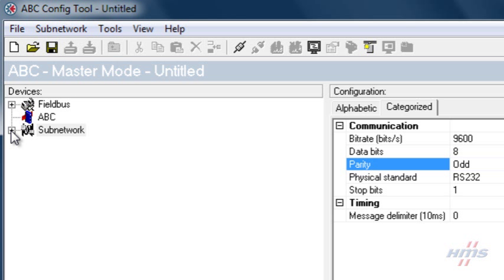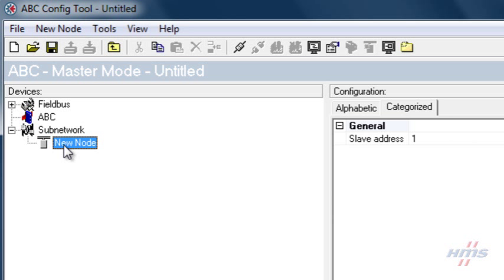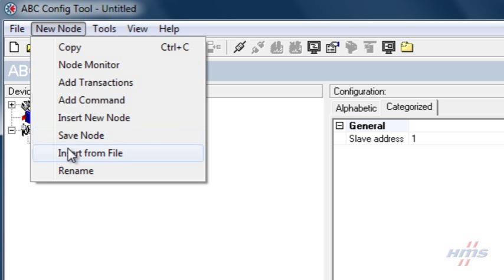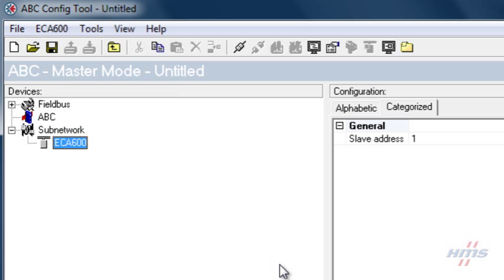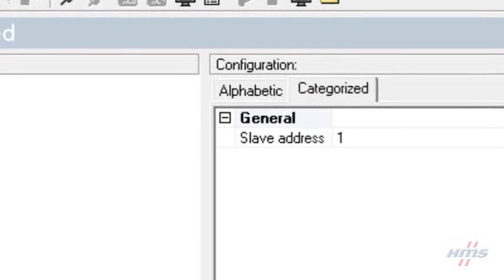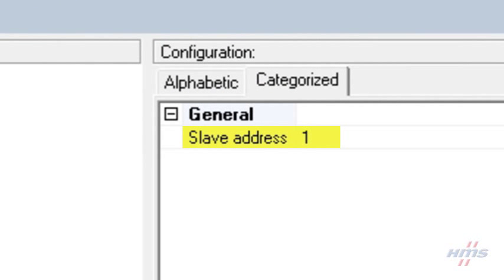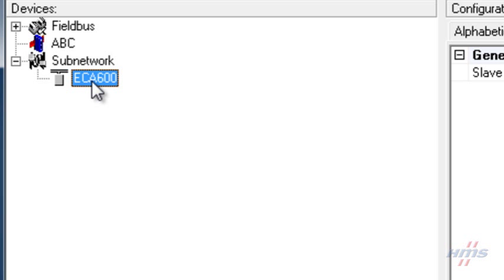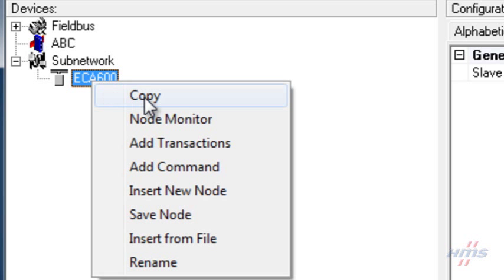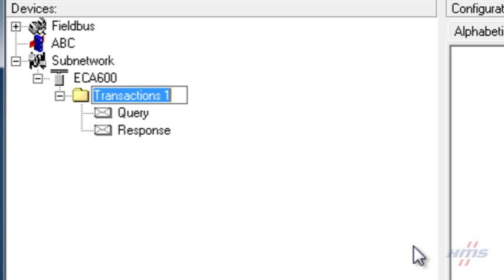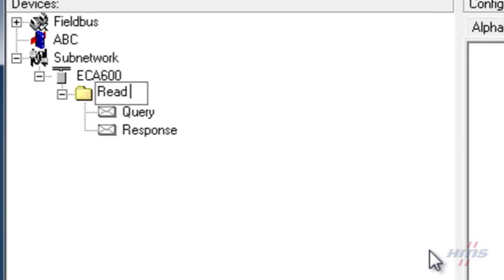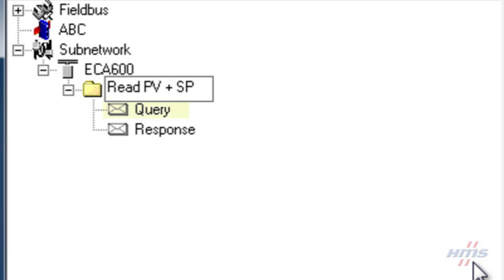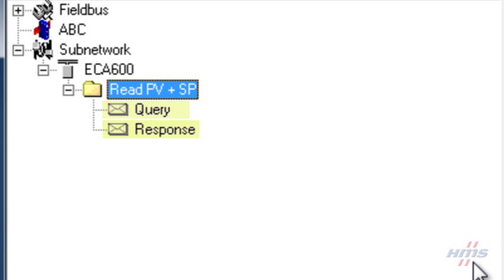We expand the subnet entry and rename the empty node ECA 600. The node slave address property is mainly used for Modbus commands and will not have any effect in our custom transactions. Then we right-click the node and select Add transactions. The transactions appear under the node and consist of a query frame and a response frame, which we will soon define by adding frame objects.